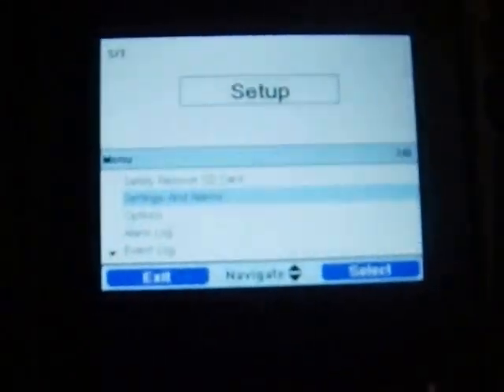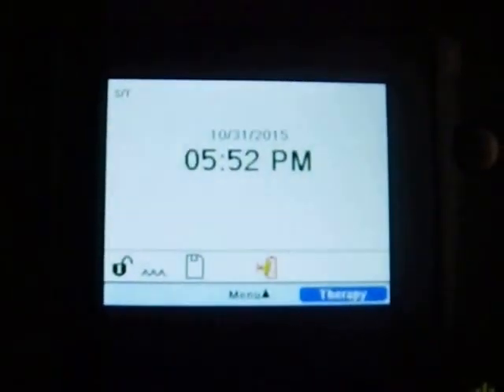Okay, I will skip telling you about alarm management here. I think I will use another video to guide you on how to set the alarms. So you can see all these settings here. Once I confirm my settings, I press finish. The machine will ask me whether I want to activate the new settings, ST mode. So I press yes. You go back to the menu. So I press exit, and now you can see the therapy button here, which means you can start to wear the mask and start the ventilation.